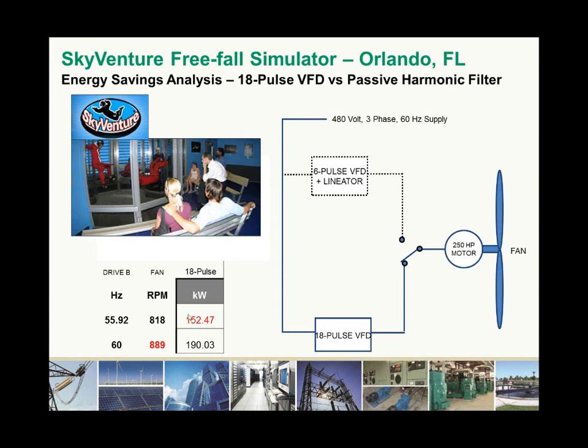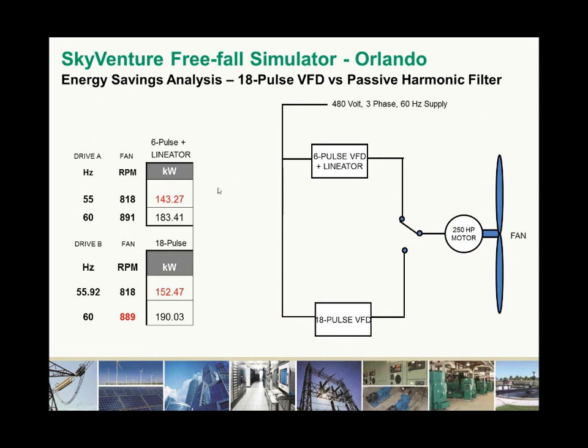When they slowed the fan speed down to 818 RPMs, which required a VFD speed of almost 56 hertz, the power dropped to 152 kilowatts. When we switched to the 6-pulse with Lineator, running at full speed, 891 RPMs or 60 hertz, the energy consumption was only 183. So you can see the reduction between the two solutions. And even further reduction, when we ran at 55 hertz, we still got 818 RPM of fan speed. So this is a fan speed that was required.